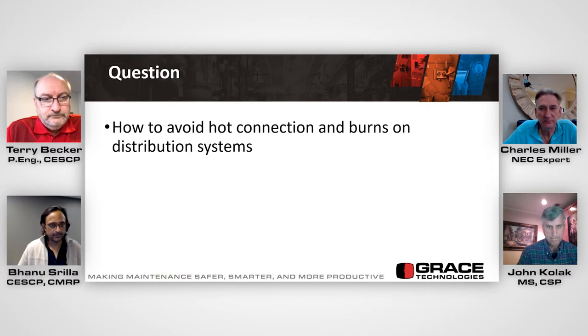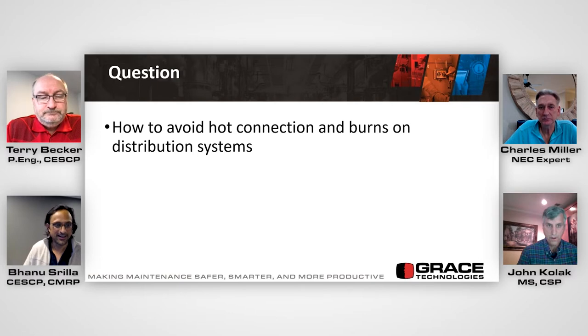You also mentioned that keeping the equipment in proper maintaining condition is also very important to keep it safer, correct? Yeah, absolutely. Especially your maintenance is important with overcurrent devices, because those have to operate at nameplate speeds. You can fudge on your maintenance somewhere else, but not on your OCPD, because if those aren't operating at nameplate speeds, those labels are wrong, understated.